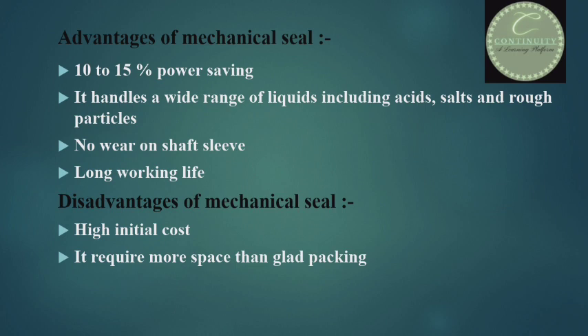Advantages of mechanical seal: it saves 10 to 15 percent power, handles a wide range of liquids including acids, salts, and rough particles, causes no wear on the shaft sleeve, and has a long working life. Disadvantages: high initial cost, and it requires more space than gland packing.